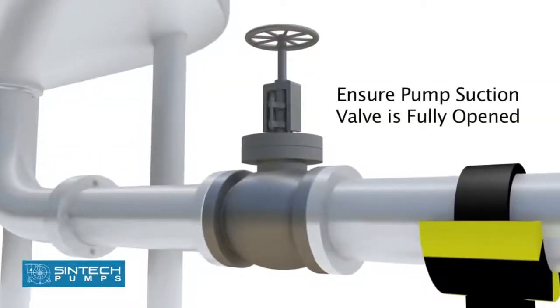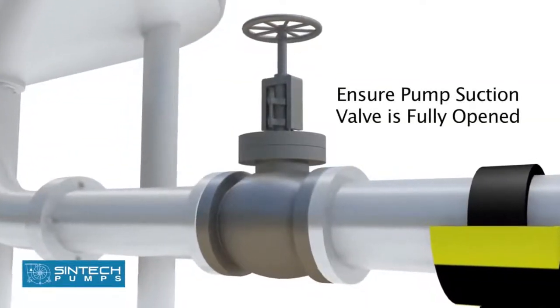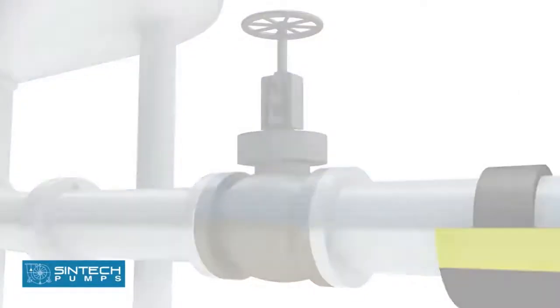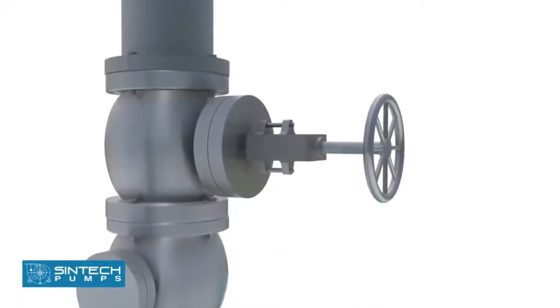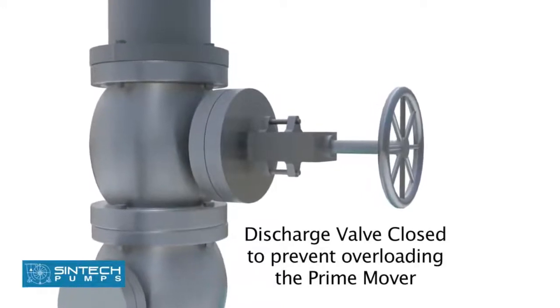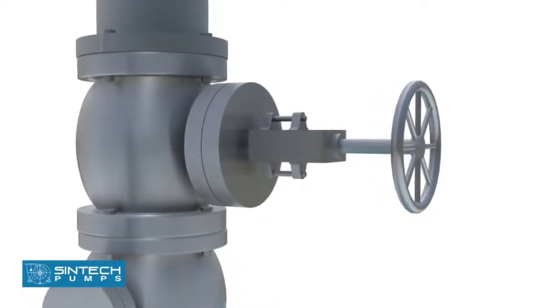Place the coupling guard and tighten the bolts. Ensure that pump suction valve is fully opened and all joints are checked for any leakage. The opening of discharge valve is kept closed as this prevents the overloading the prime mover.